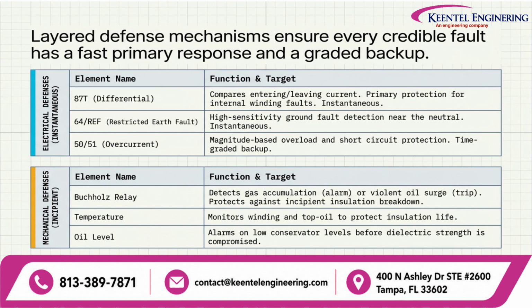The transformer also has important mechanical and condition-based protections. The Buchholz relay can detect gas accumulation associated with developing internal problems and can also respond to sudden oil movement associated with more severe faults. Temperature monitoring provides protection against excessive winding and top oil temperatures, and oil level monitoring can provide an early warning before insulation performance is compromised. The important concept is redundancy. No single protection element should be expected to handle every possible failure mode.